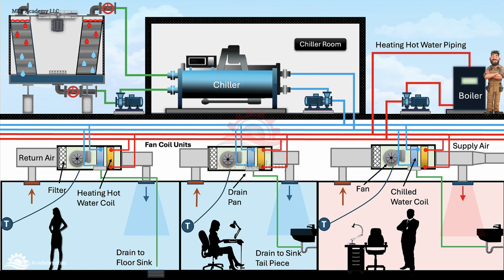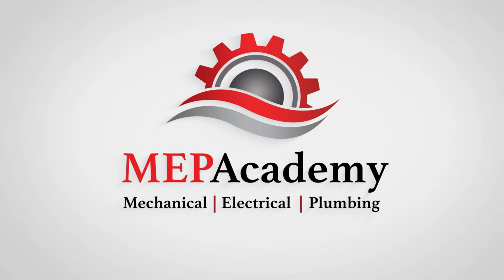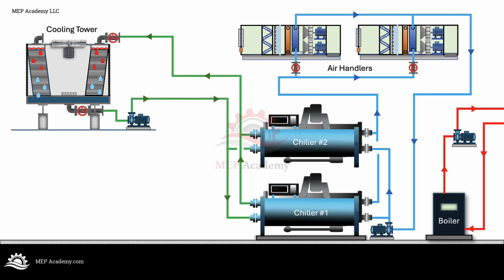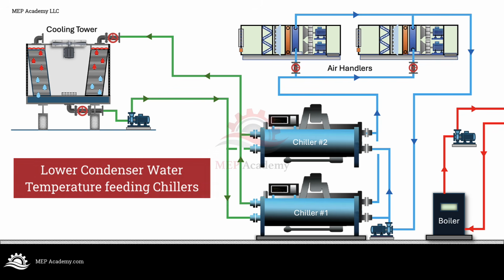Instead of treating condenser heat as waste, a heat recovery chiller captures that heat and sends it to a useful heating load. That is the basic idea. In this video, we'll look at two heat recovery chiller designs. Now let's look at the first application. In this application, the heat recovery chiller is used to lower the condenser water supply temperature feeding the main chillers.